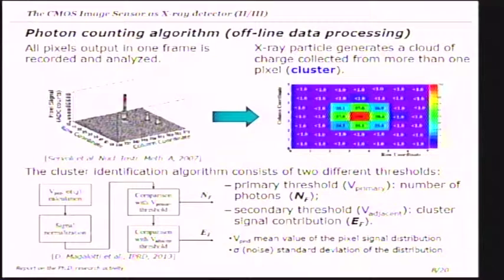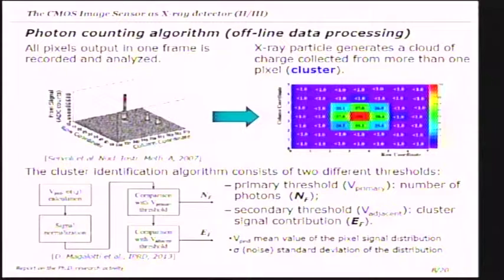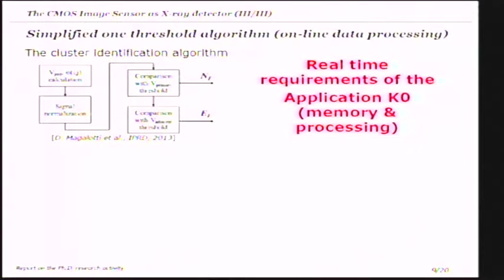A cluster identification algorithm has been considered to find the observables correlated to the dosimetric quantities. This cluster algorithm consists of the following steps: first we evaluate the pedestal and the noise distribution of all pixels in the sensor frame, then we normalize each pixel and compare it with a primary threshold to identify the number of photons in a frame, and with a secondary threshold to identify the cluster signal contribution. These two observables are correlated to photon energy and absorbed dose. However, implementing this algorithm in a modern programmable device requires a lot of memory resources to store all pedestal and noise values for each pixel, and a lot of digital processing resources to implement the divider operation for the normalization.